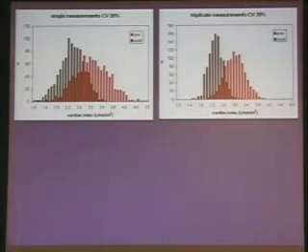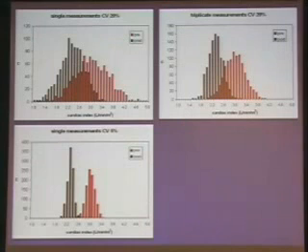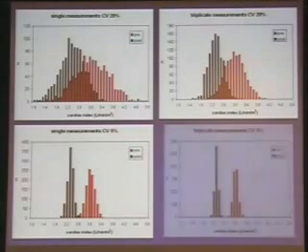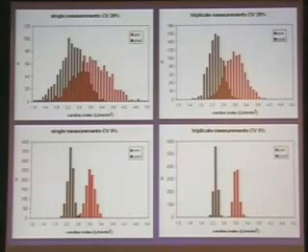If you take another tool which has a much lower coefficient of variation, like, for example, the PiCCO or transesophageal Doppler, their coefficient of variation is down about 5%. Sorry, I should say the PA catheter in ideal hands is somewhere between 10 and 15%. In reality, it's probably closer to 20, so that's the PA catheter. This is the PiCCO, Doppler, and a few other techniques, where the coefficient of variation is 5%. There's much less overlap, and if you do triplicate measurements, there's almost no overlap. So I think that illustrates the point.